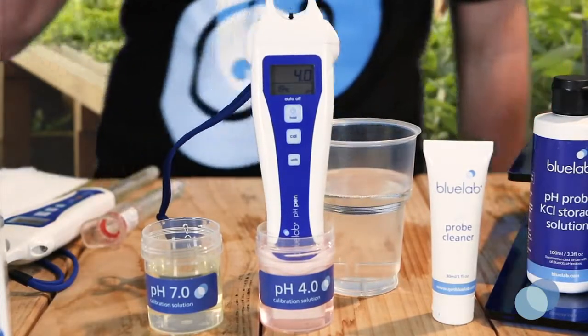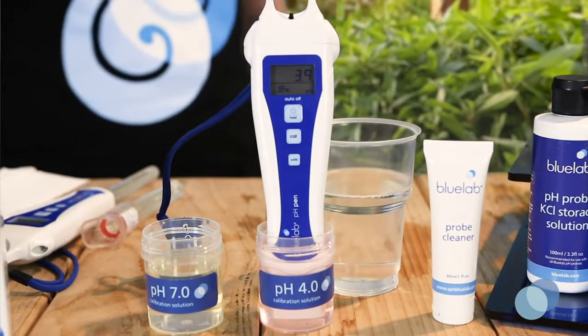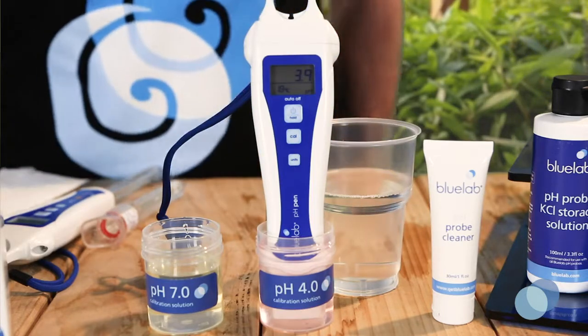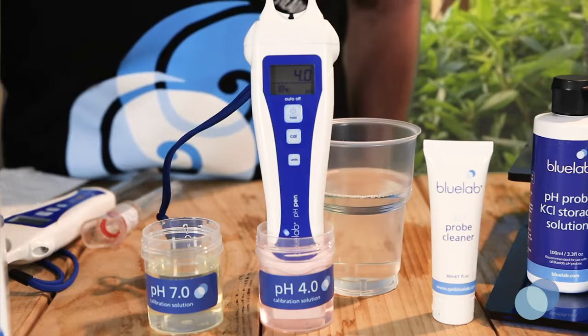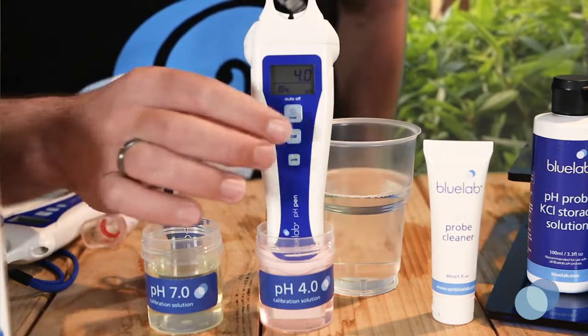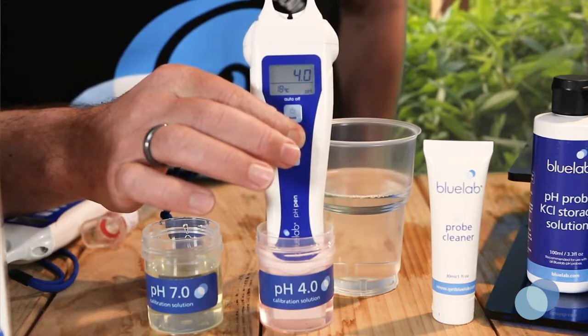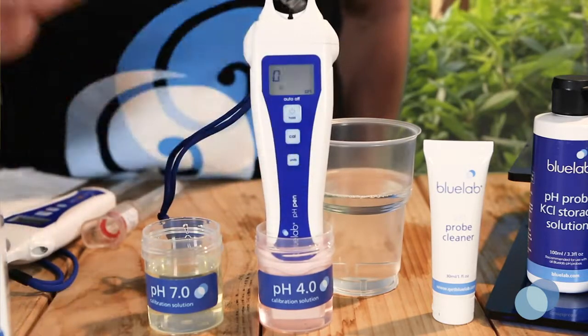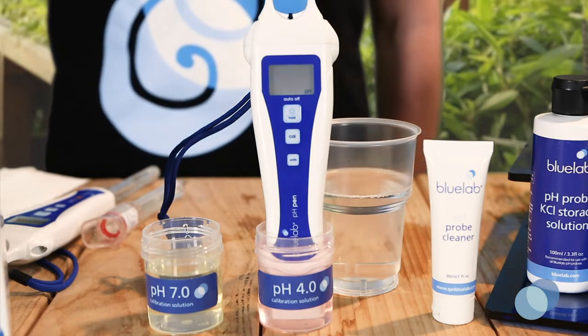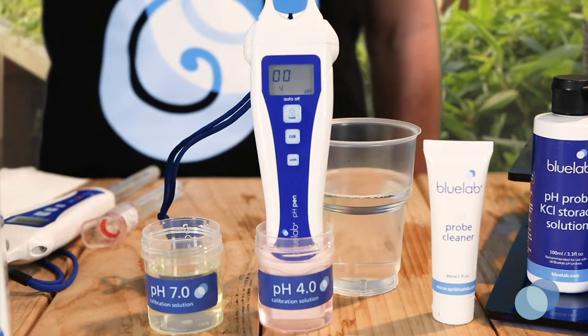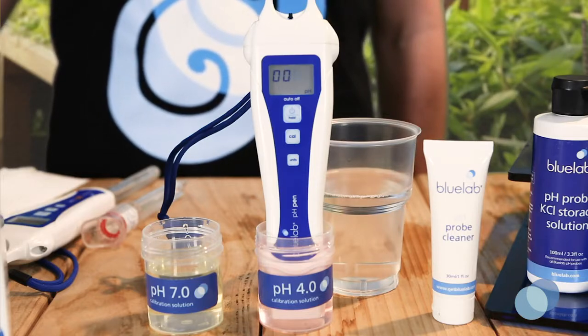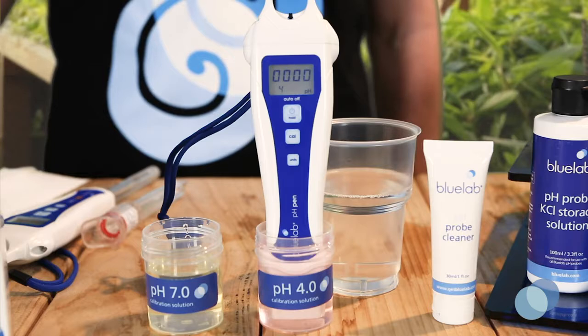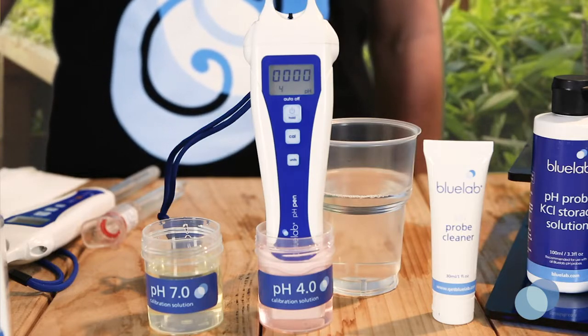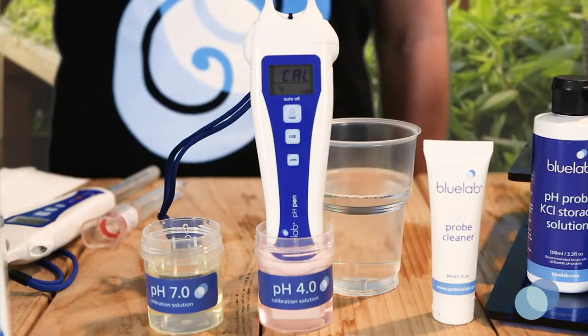Give the probe a gentle swirl to ensure you've got good contact between the probe glass and the calibration solution. Then wait for the reading to stabilize. Press and hold the Cal button until Cal is displayed on the screen. Then release the button. Four small boxes start to flash, indicating the start of calibration. Leave the probe in the solution while the display is flashing. After the four boxes stop flashing, Cal will display on the screen, letting you know that calibration is complete.